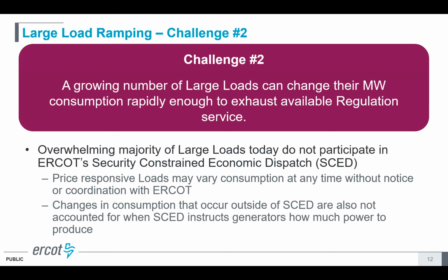What we're seeing now is we have all these loads that are capable of ramping their full consumption within a 5-minute SCED interval, some as fast as 90 seconds. They have roughly the same kind of pricing behavior in terms of what triggers their response, and as a result, in aggregate, these large loads can actually ramp enough to exceed the available frequency regulation procured for the interval.